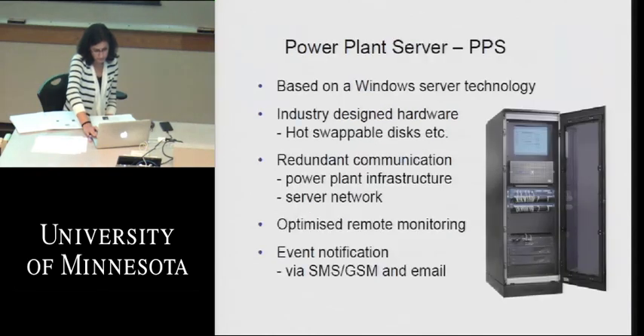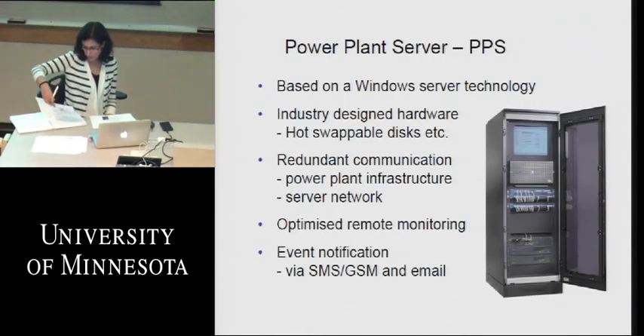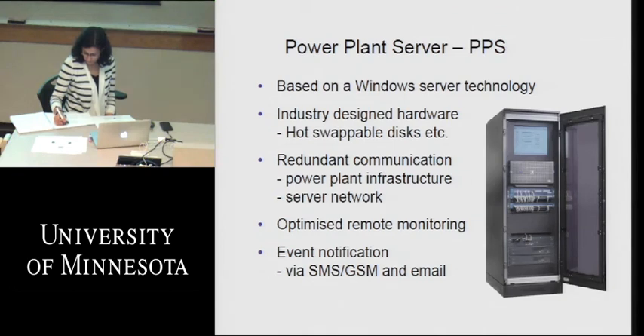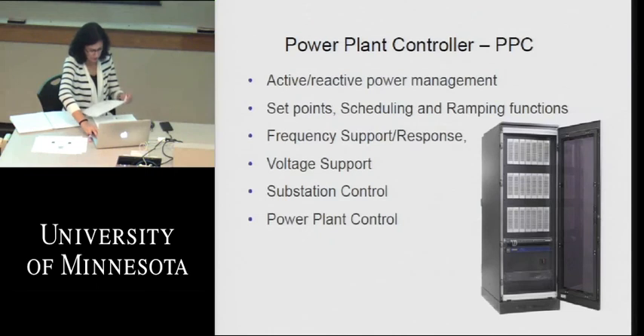Next slide shows the power plant server, which is a PLC-based converter that actually works with the SCADA computer server, but its only function is to give power plant control and not a lot of reporting in and out or interconnection with the outside world here. But it affects the frequency and the voltage control and other control functions you want the power plant to perform. So next slide, a little bit more of the type of functions and controls of the power plant controller.